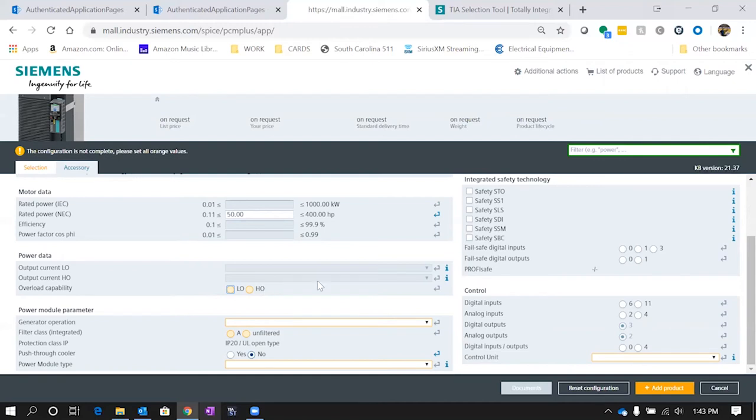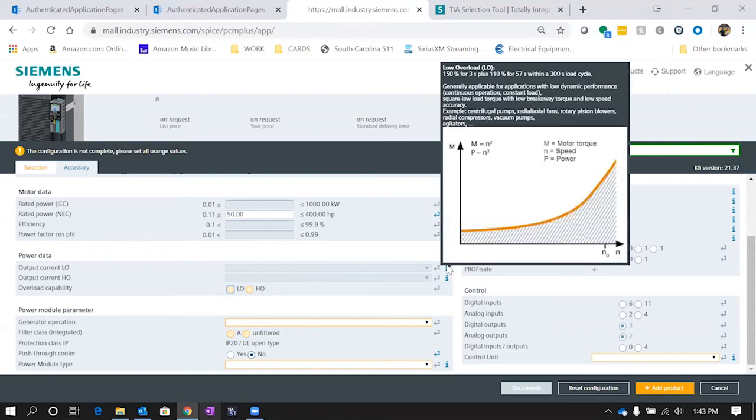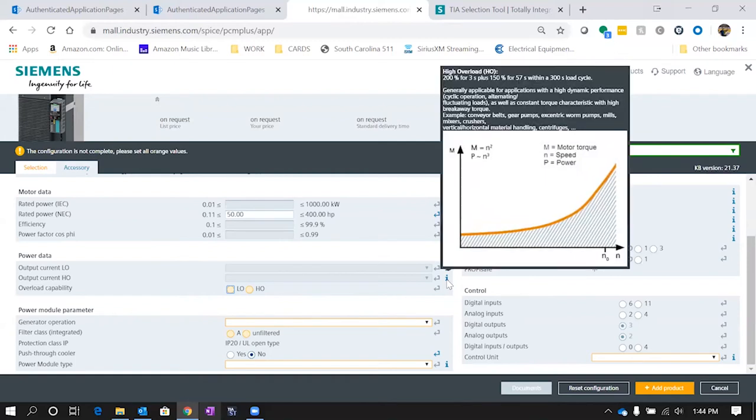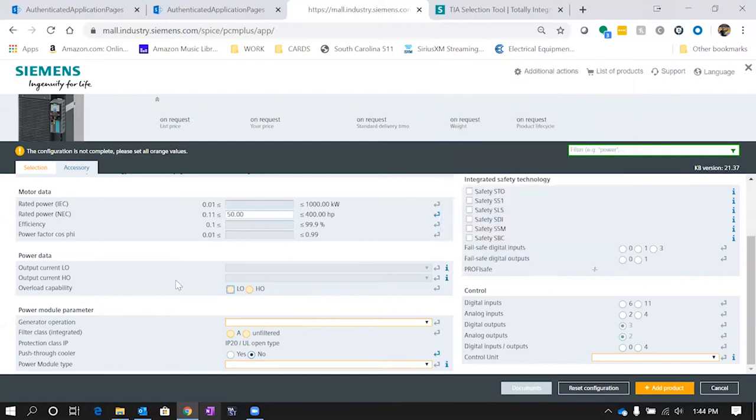Now it's asking if you want low overload or high overload. Remember we're dealing with a pump. If you don't know the difference, it has to do with the amount of overload and how long the drive can sustain it. If you hover over the i, it gives you information. Low overload is 150 percent, more for pumps and fans, whereas high overload is 200 percent for three seconds, more geared for conveyors, worm pumps, things where you need a lot of torque to get going. We're going to pick low overload and it fills in those current values.